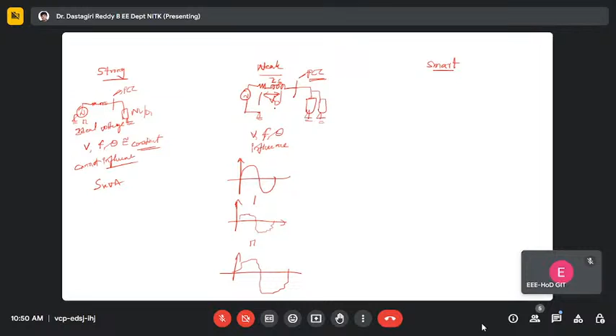So that's the problem with the weak grid. You can also define strong and weak using the short circuit capacity, SKVA rating—short circuit capacity or short circuit current. The maximum installed power allowed at a particular location is decided by the short circuit capacity. So weak grid means you have less short circuit capacity.